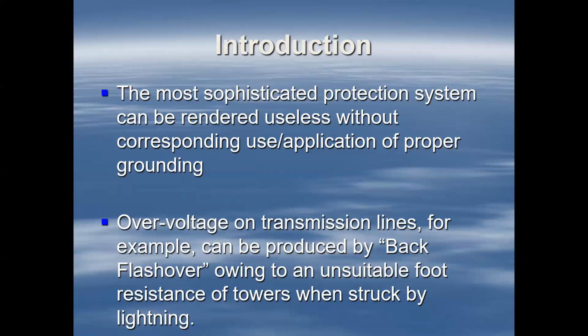One of my past major projects looked at the earthing problem persons were having in the Red Hills area, the upper part of Red Hills Road. In one instance, and I tell this story every time I come to this point, we went to a light pole and were testing the resistance on that earth wire. At the base of the light pole, we were getting fairly good readings, below 10.